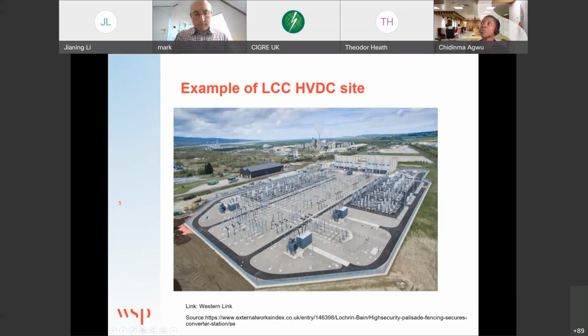So this is, for example, an LCC converter station. This is one of the ones which was mentioned in an earlier presentation. This is Western Link, which connects the western side of Scotland to Wales. It's a bipole scheme which can transfer 2,200 megawatts. That's your one pole on that side. That's your other pole. This area here is all of your harmonic filter. So this is your AC filter, which is going to clean out your harmonics. This area here is your harmonic filter for that pole, and that's your harmonic filter for the other pole. So straight away, you can see the amount of space that is taken up by harmonic filters.